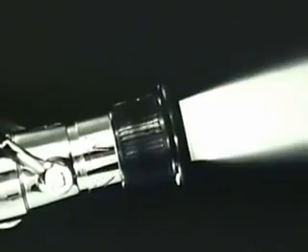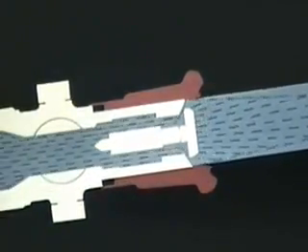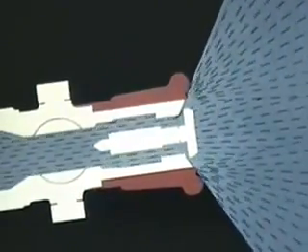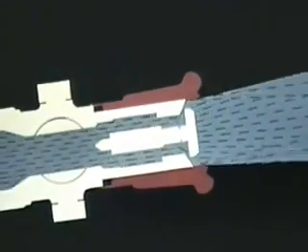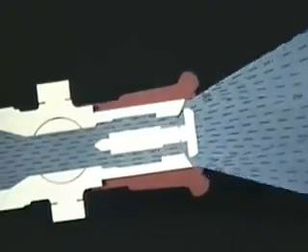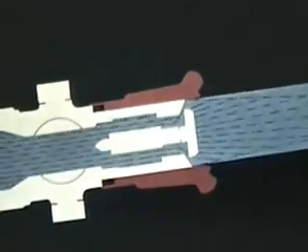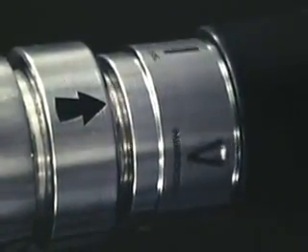As a nozzleman, you should have an idea of the mechanics of its operation. With new constant gallonage nozzles, your flow in gallons per minute is the same in all positions. These nozzles are designed to operate at about 100 pounds nozzle pressure. Most nozzles have marks or notches which serve as a guide to indicate the degree of fog.